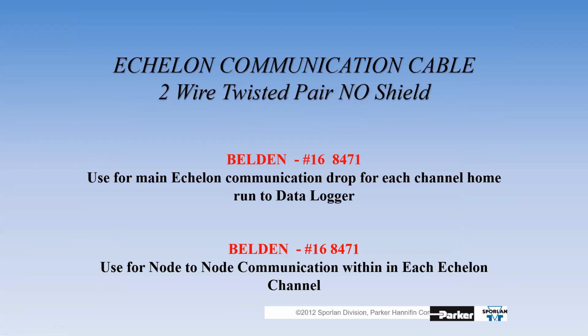So what do we use differently? If you're not familiar with it, a lot of other modalities use a light gauge, 22 or 24 gauge communication cable with a foil shield or a drain wire shield. That is a big no-no for echelon.